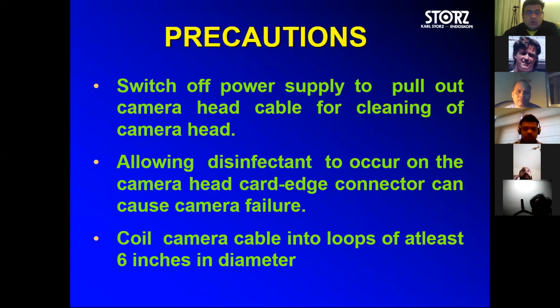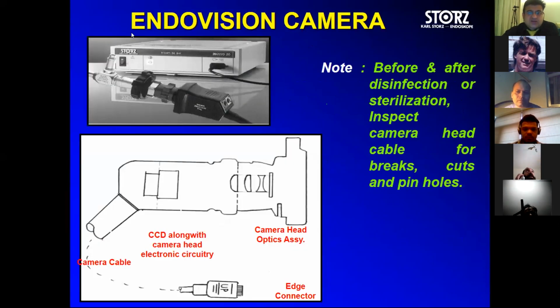Now there is also what is called a card edge connector. Now if you see the cable here, when you take out this cable, many times the paramedical staff are not conscious, it falls down. And here on the surface, you'll find there are 10 electrodes on the top and below. That means there are almost 20 electric wires which are running through this. And by dropping it, it can get damaged on the edge. You still get an image, but you're not very happy.